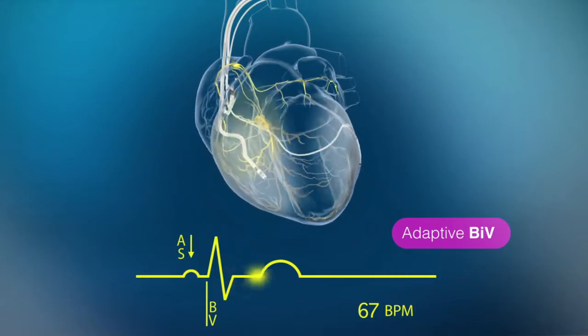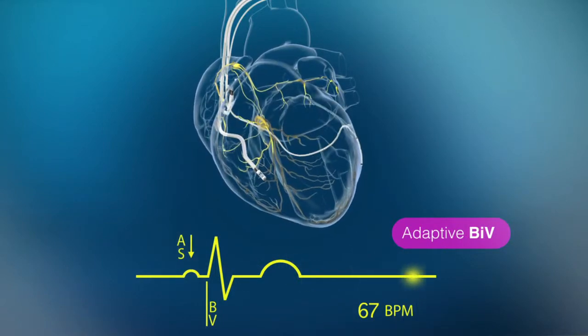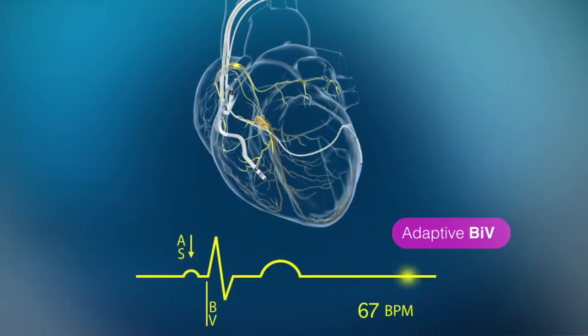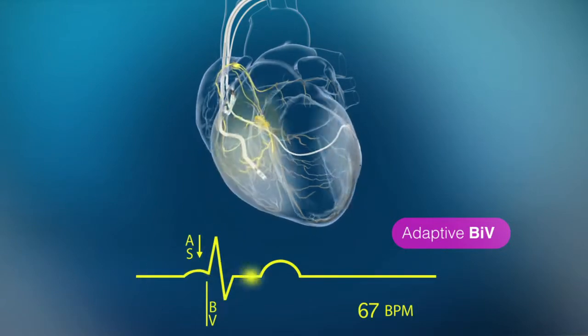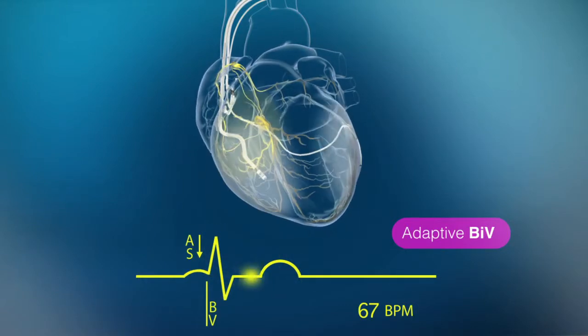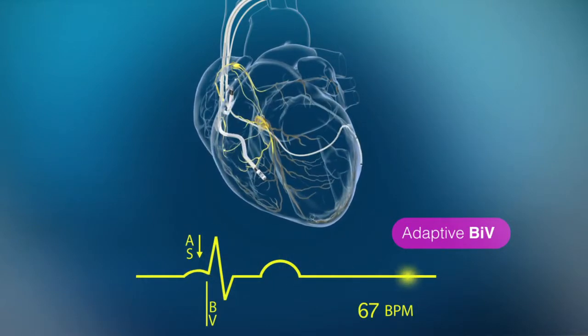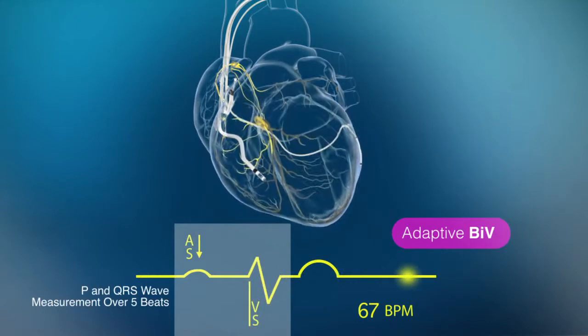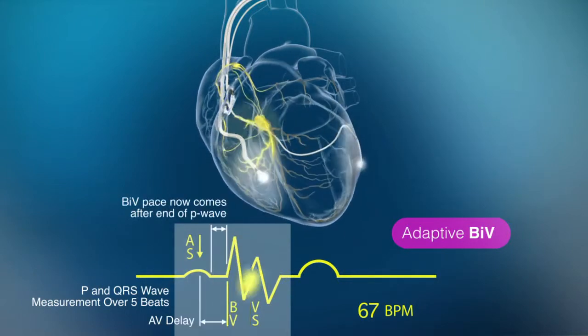Atrioventricular synchrony, in turn, requires the left ventricle to contract after the left atrium. The timing of the contractions can be determined by measuring the duration of the p-wave and adjusting the atrioventricular delay accordingly.